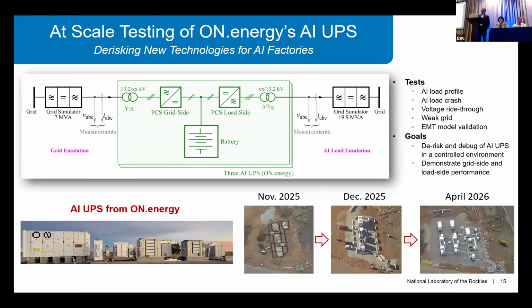Having two grid simulators at the lab and all these testing capabilities like AI load profile emulations, impedance scans, and voltage jump makes us a good fit for testing such equipment, where we need a two grid simulator approach, one for emulating load transients and one for emulating grid disturbances like low voltage, and to do it simultaneously. And at the bottom, you see one branch of this UPS, basically battery and two converters. Right now, we are actually testing three branches. So we started with testing one branch of UPS, and now we are going to start testing with three branches of UPS in parallel.